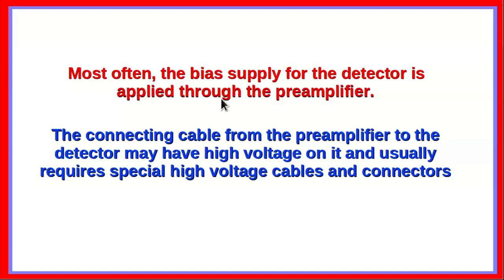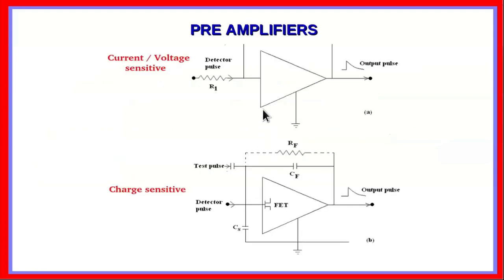Often the bias supply for the detector is also applied through the pre-amplifier, with a separate connector for this purpose. The connecting cable from the pre-amplifier to the detector may carry high voltage, requiring special high-voltage cables and connectors. These circuit diagrams indicate the two main types of preamplifiers: the current or voltage sensitive preamplifier, which converts detector current to an output voltage pulse, and the charge sensitive preamplifier, where the output pulse is proportional to the charge collected at the detector terminals. Both use an FET input stage to reduce noise.